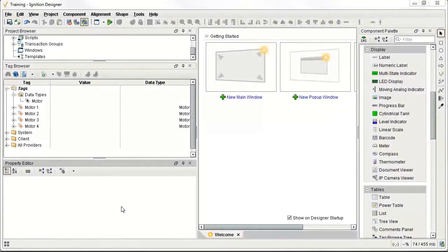Complex tags, or UDTs, user-defined types, are really important in Ignition. Complex tags are actually created out of standard tag types, but they offer a variety of additional features. In simple terms, you can think of them as a way to create a data template, where a particular structure of tags is defined and can then be created as if it were a single tag.